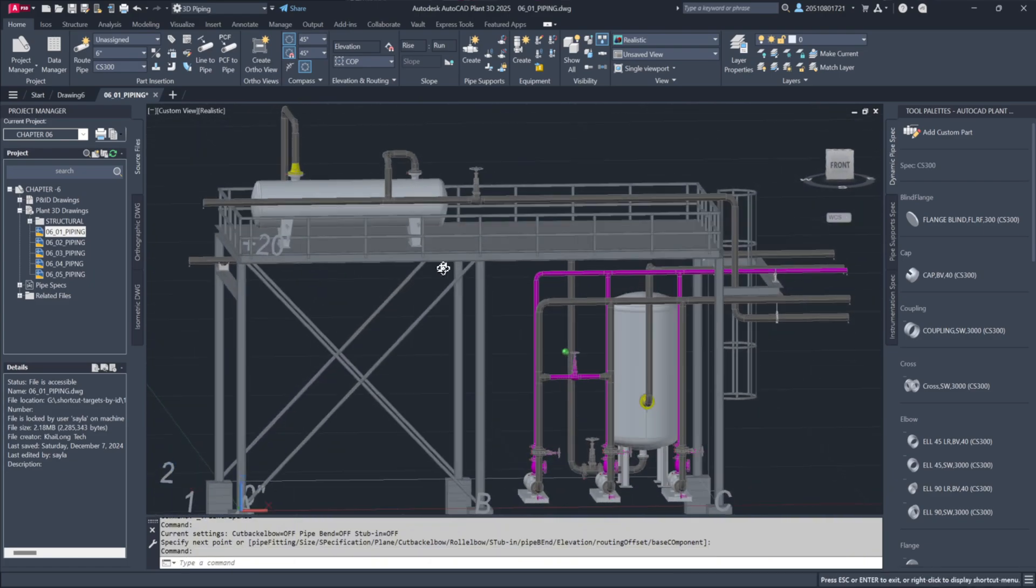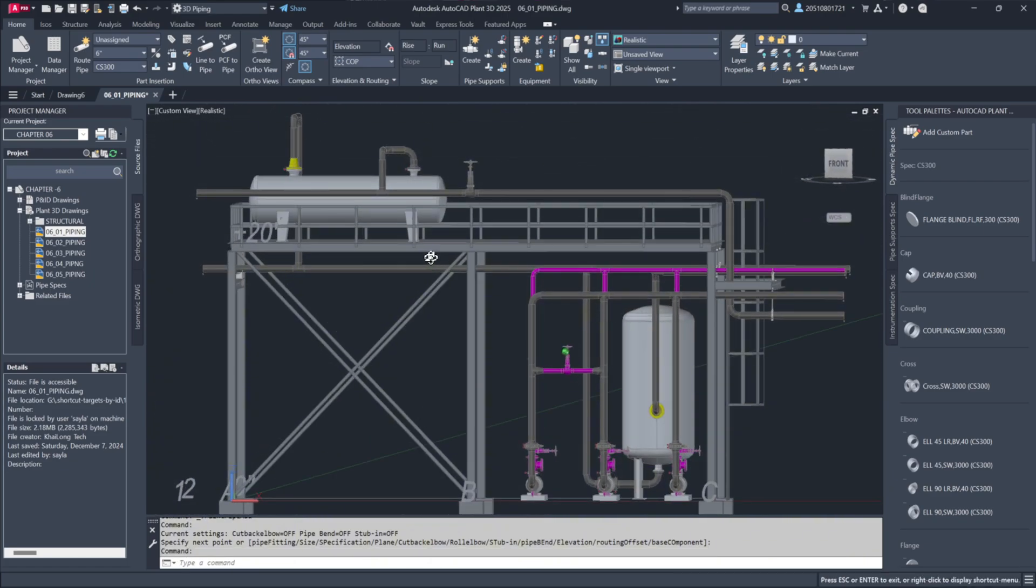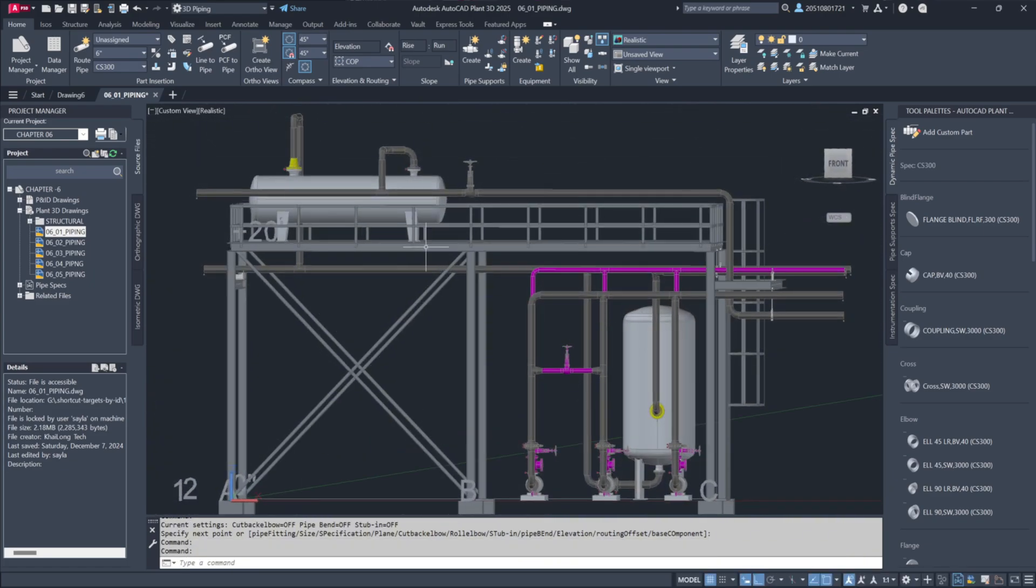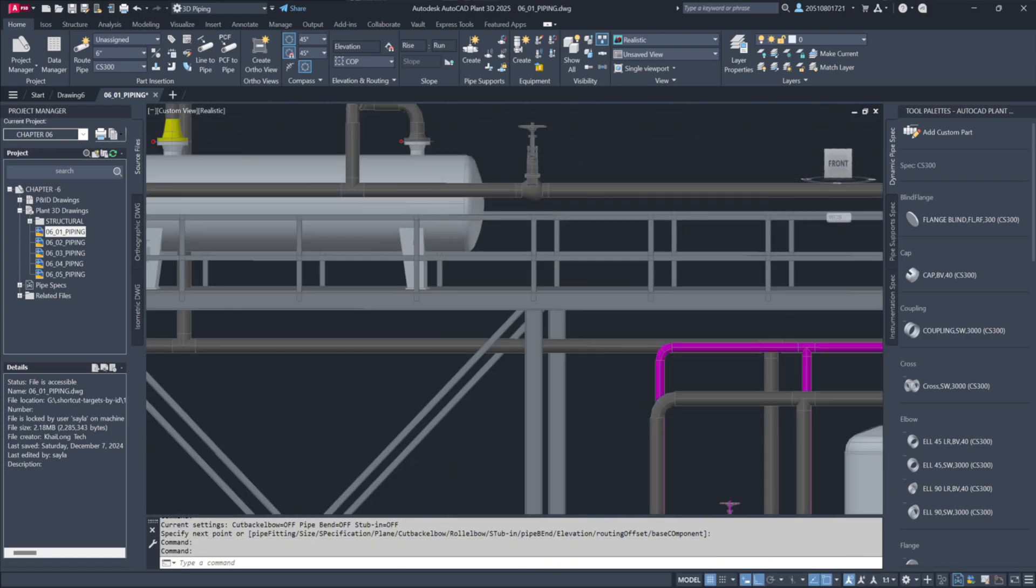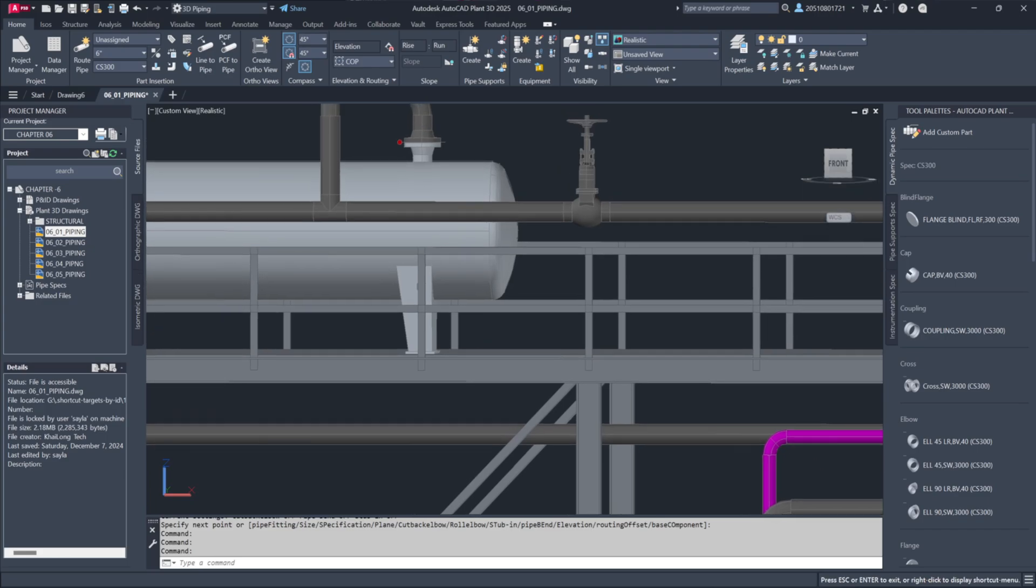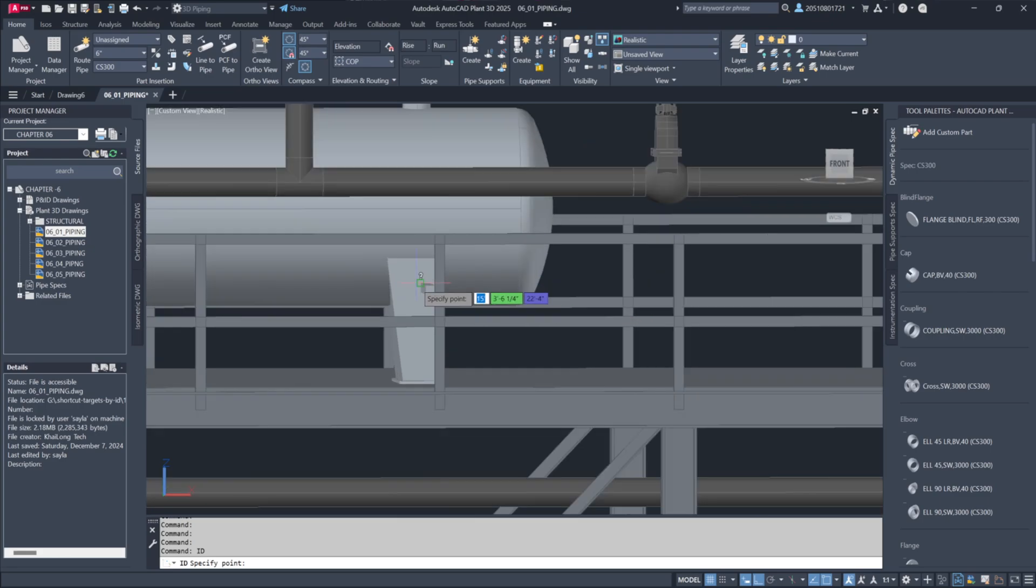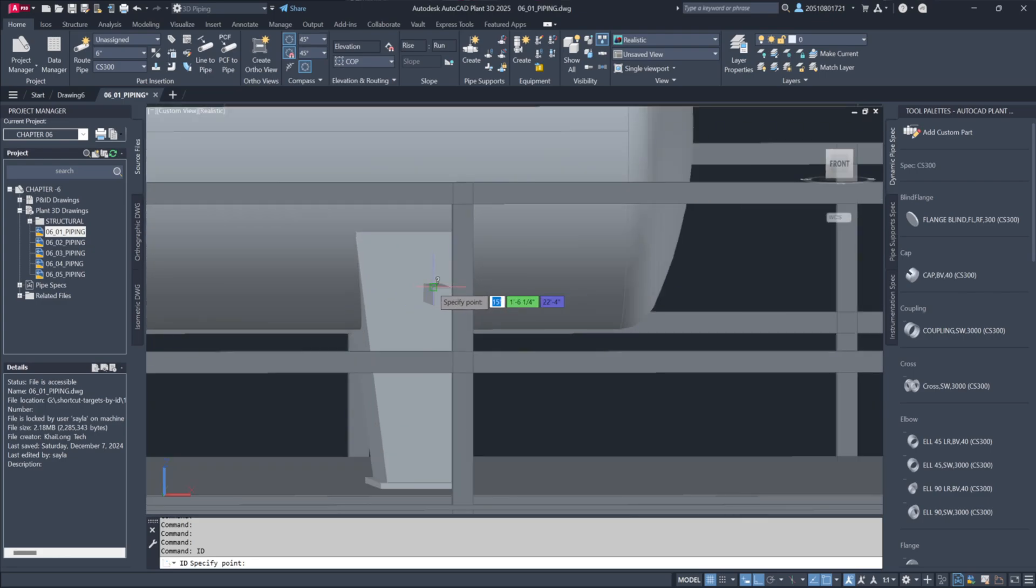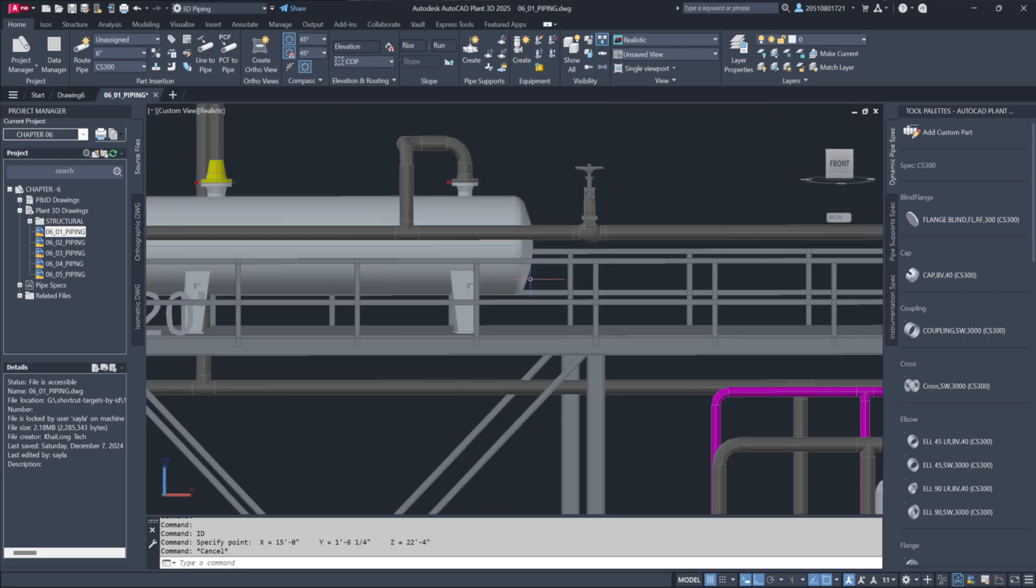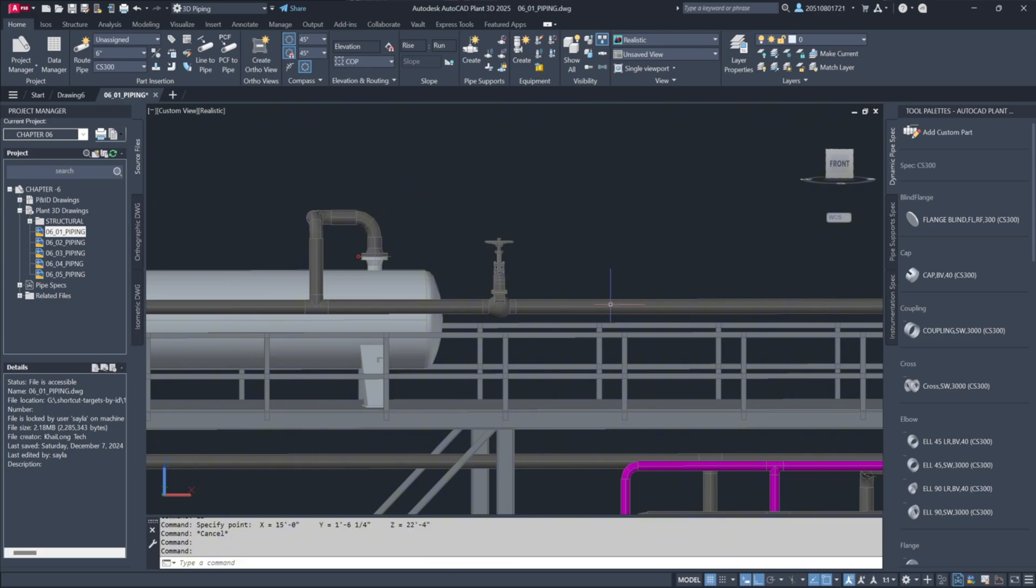With the additional pump installed, let's adjust the pipe elevation. Some pipes are floating, so we'll lower them to rest on the structural steel. Use the Dynamic Input feature to select the desired elevation. By identifying the top of the steel as 22 feet 4 inches, I'll adjust the bottom of the pipe to match this height. AutoCAD makes precise placement simple.